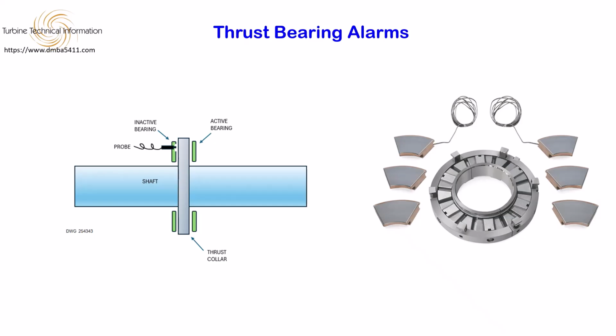Then if the alarm is 0.003 of an inch of wear into the bearing, 200 mV multiplied by 3 gives 600 mV, which is added to or subtracted from the voltage obtained when the rotor was at the extreme of its travel.